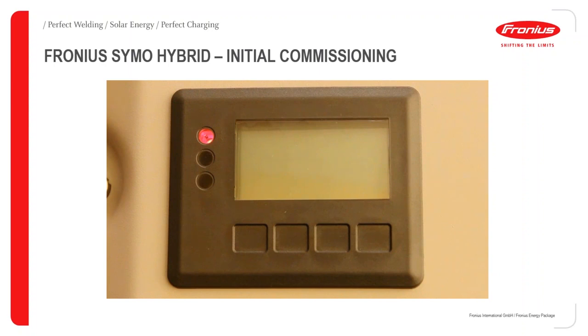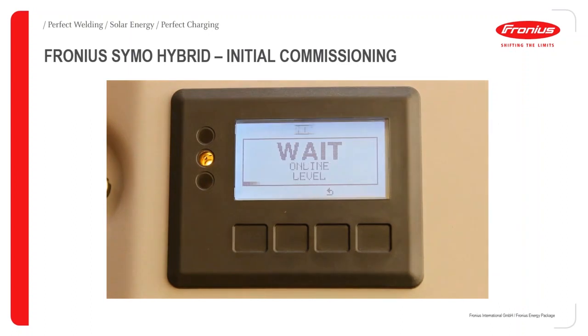So when you press English, it'll say wait, and it'll ask you to select the country setup. In Australia, some people get confused with using the 50 Hertz. Australia is 50 Hertz, but you want to select Setup Australia. When you do that, it'll take about 30 seconds or a bit longer to load the country setup. All the lights will flash on and off, and then it'll come up with wait master ready or wait communication. And if there's DC connected, it'll start up.